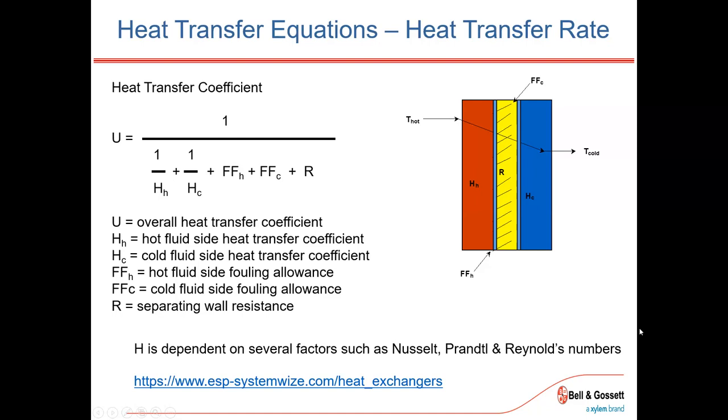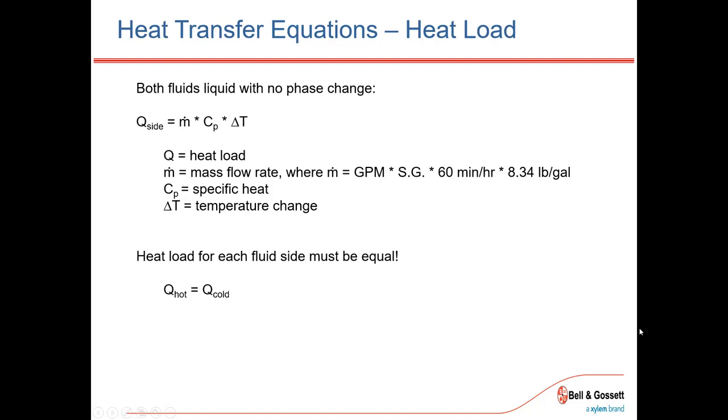Right here, we are calculating our mass flow rate. So we're looking at our load. When we take a load, what George and I have done in our class, a lot of times we'll simplify things and say 500 times the delta T times the GPM will give us our load. When obviously that load depends on many different factors, right?